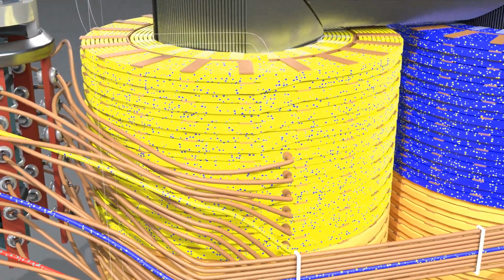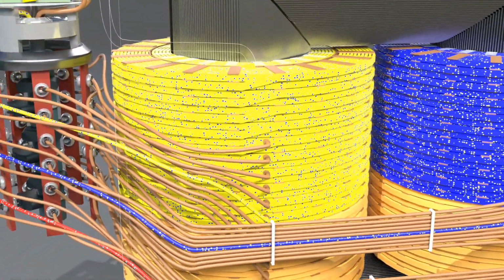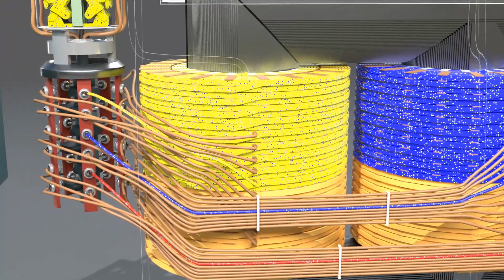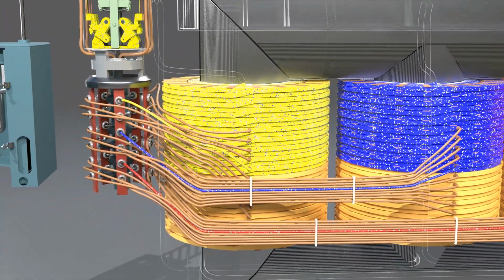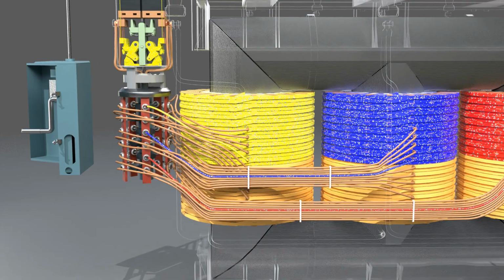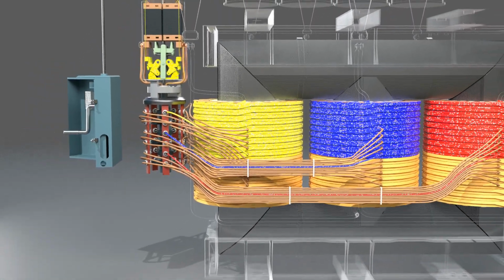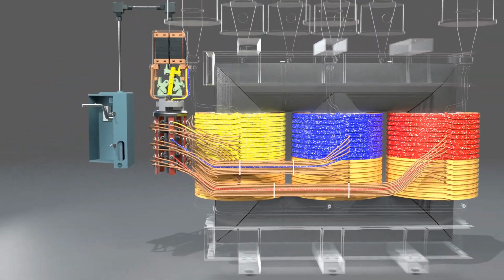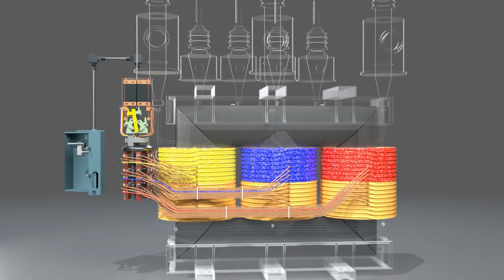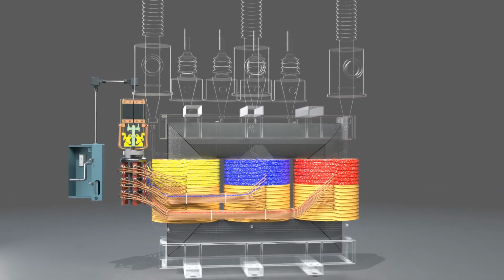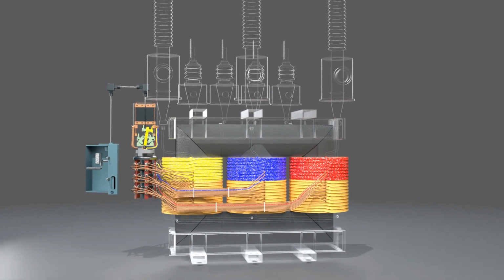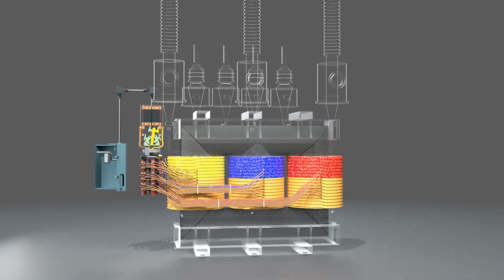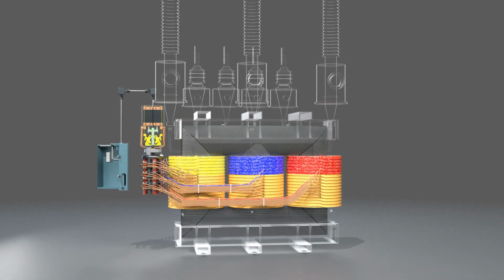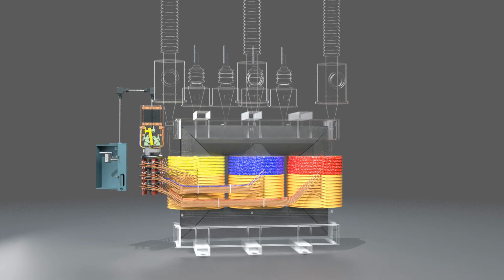When the voltage on the load side is higher than the desired value, the tap changer moves the arm toward a higher tap number on the winding. Higher tap number equals lower turns in the secondary winding, lower turns equals lower voltage output. As the tap is changed, the transformer effectively reduces the number of active turns on the secondary side, which steps down the voltage to the desired level.